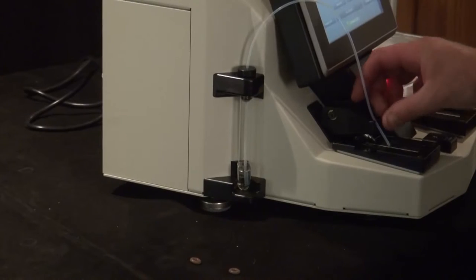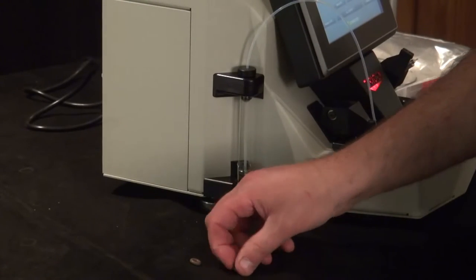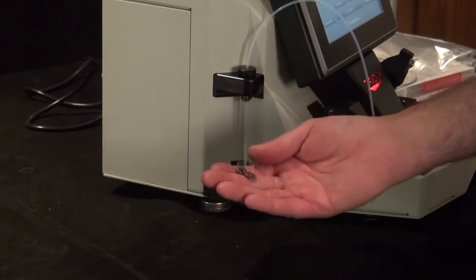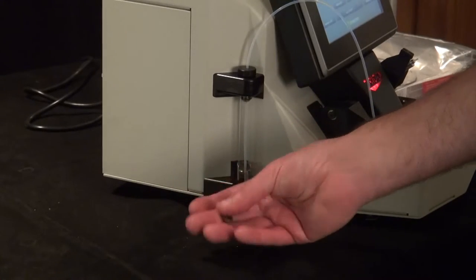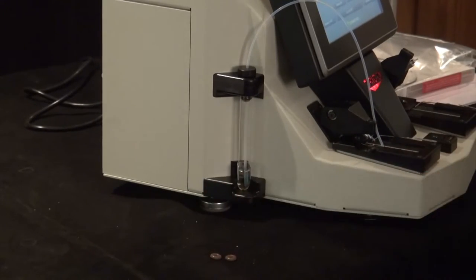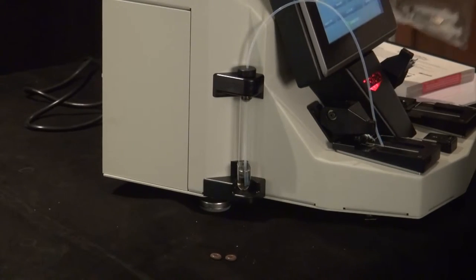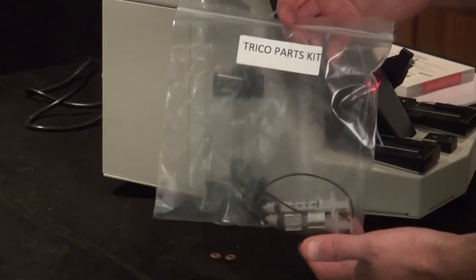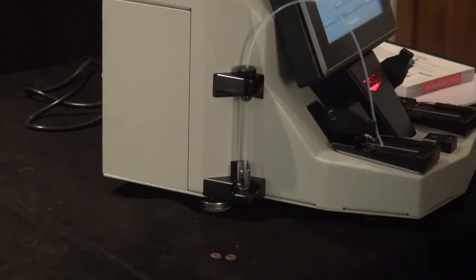What you want to do is go to your parts kit and get replacements. You might as well replace all the seals right away. You're going to grab the two large o-rings, which are Viton, and then there's two small tiny o-rings inside your Trico parts kit that you want to grab out of there.